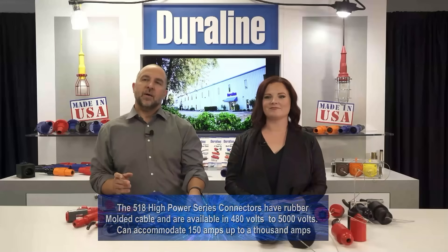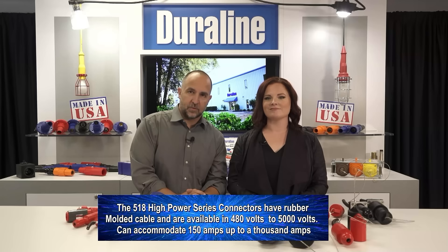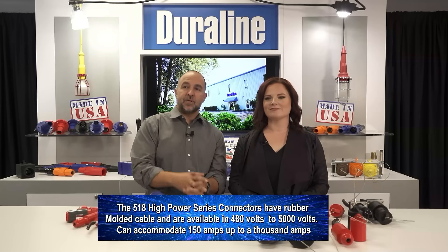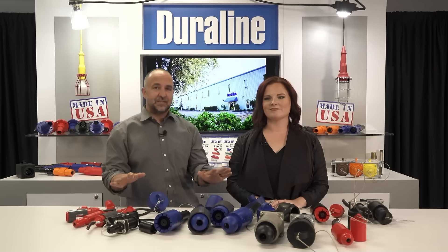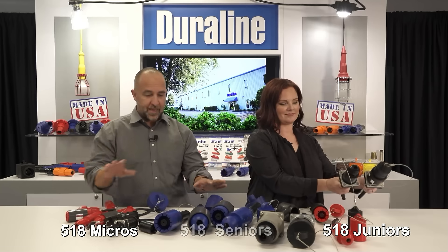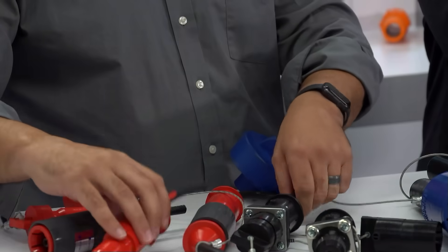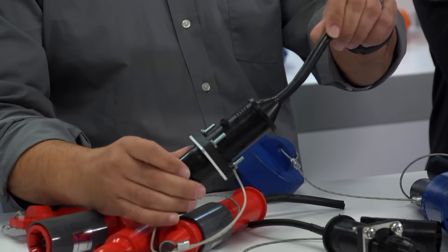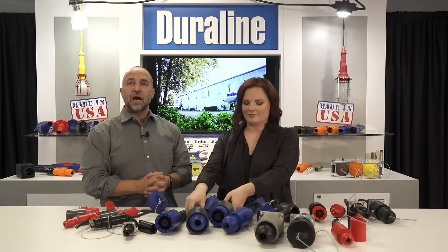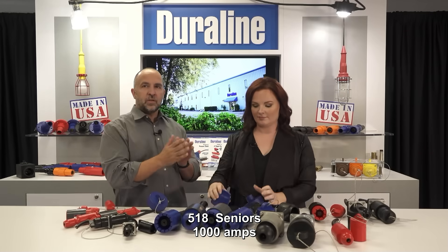The 518 high power series connectors are rubber molded to cable and are available in 480 volts to 5,000 volts, and can accommodate 150 amps up to 1000 amps. There are three different series in this family: 518 micros, juniors, and seniors. They are available as inlines and receptacles. We put the locking ring on the male or the female depending on how we're configuring the system. The seniors are used for 1000 amps, the junior is for 300 amps, and the micro is 150 amps max.